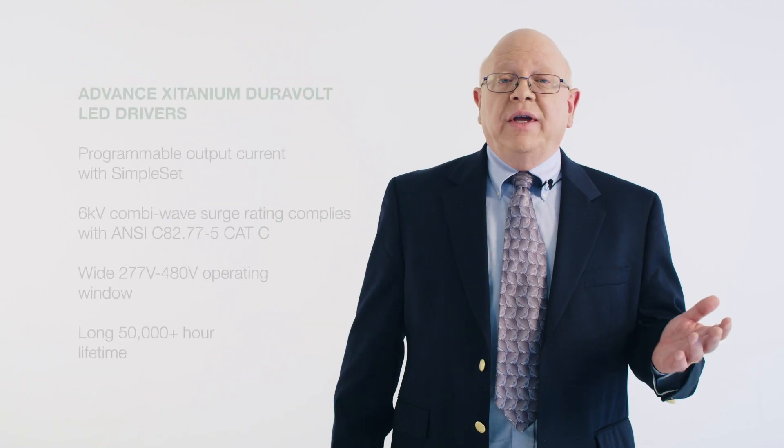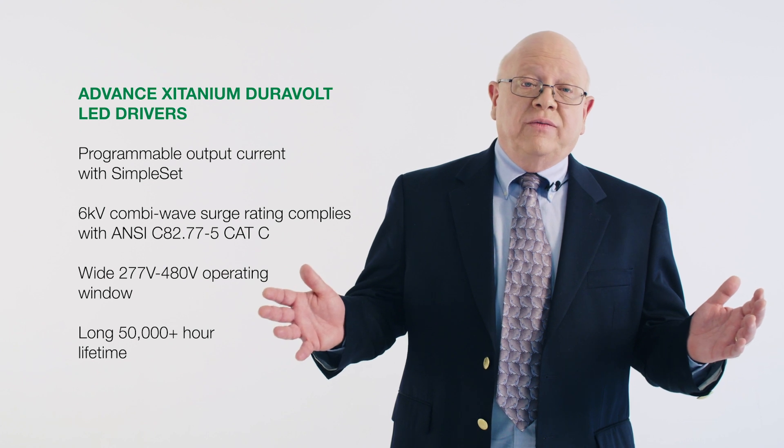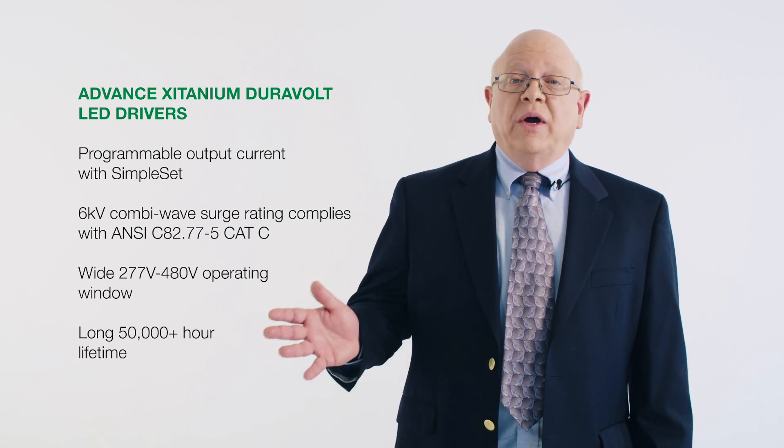Duravolt drivers enable long-life luminaire designs with a wide variety of loads and adjustable current options, and they deliver the same high quality and rich features of our proven line of Xitanium drivers. These include programmable output current through SimpleSet, a 6 kV combi wave surge rating, a large 277-volt to 480-volt operating window, and a 50,000-plus hour lifetime.